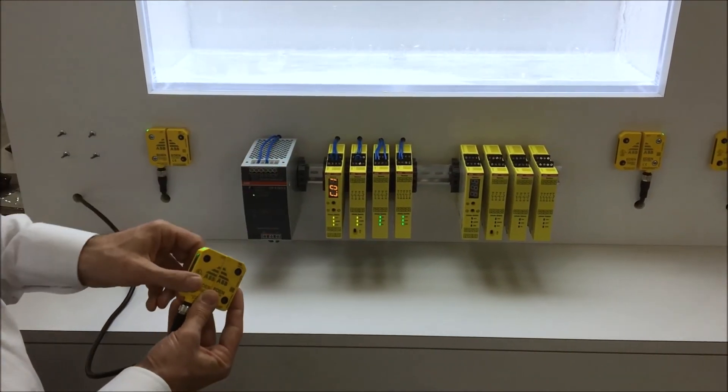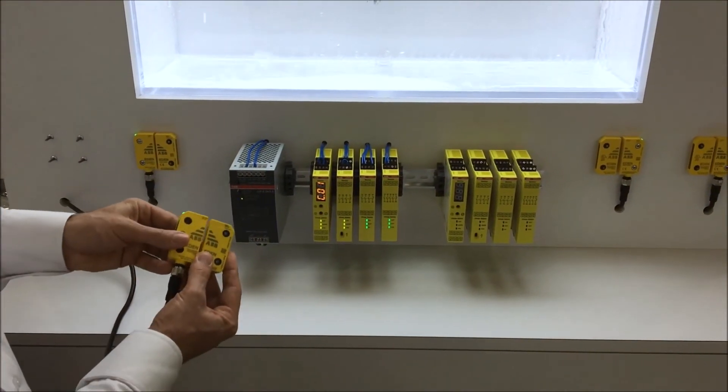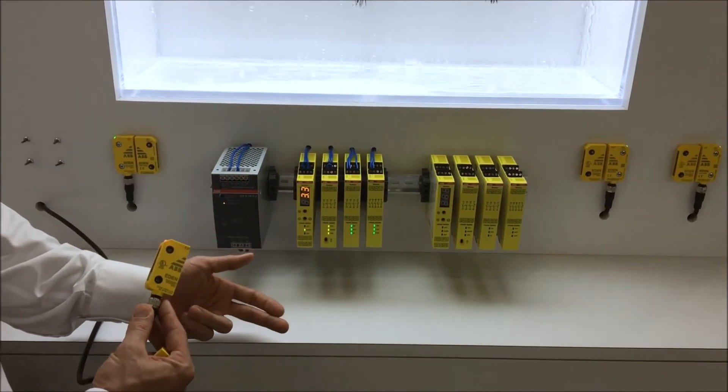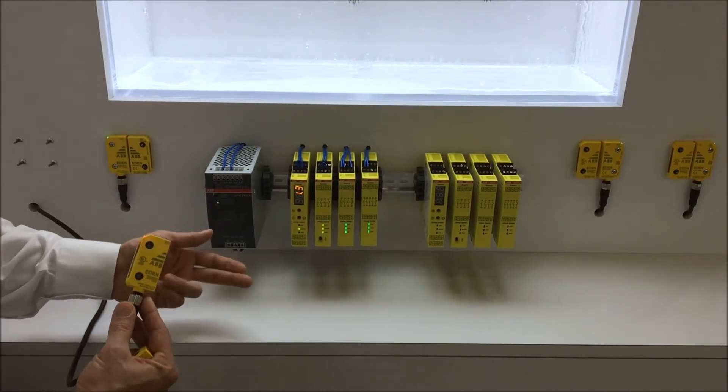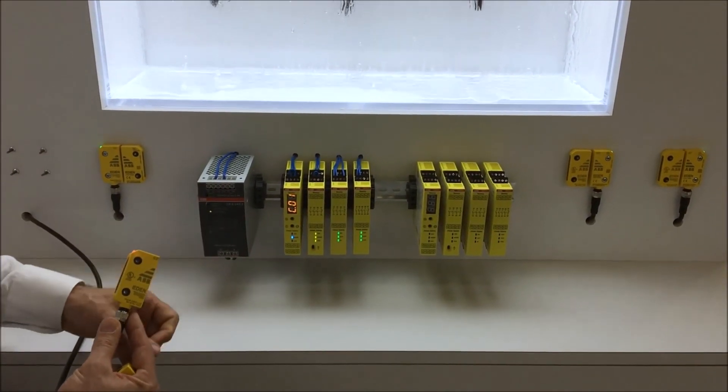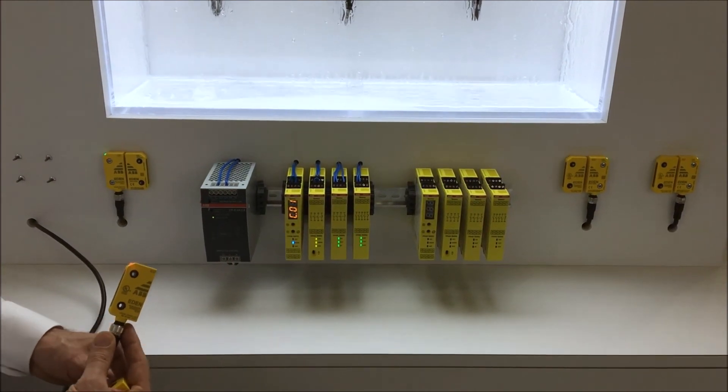This particular relay is set for an off delay. When I open my door, I will be sending a stop signal to the drives, possibly to the enable, to allow it to stop. Within a time delay, I then will drop my secondary output which will go directly to the contactors killing power to those motors.